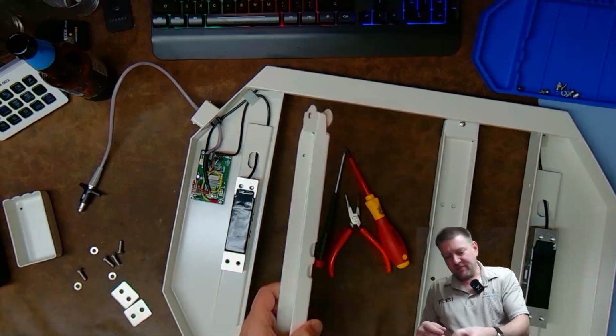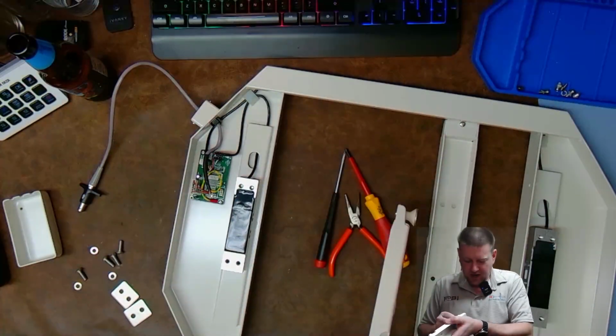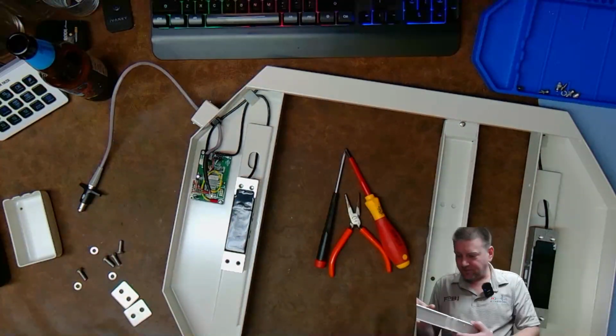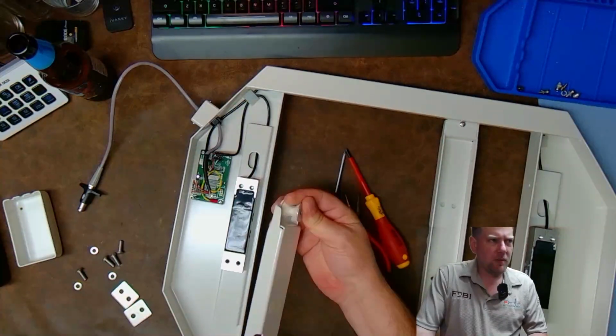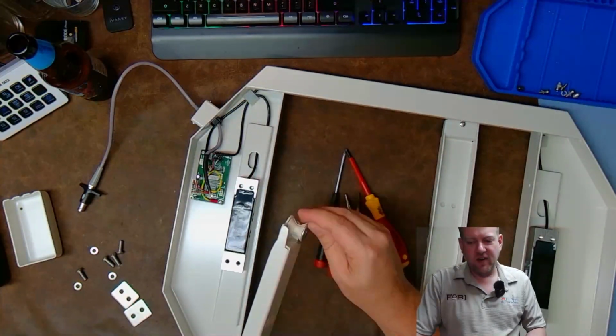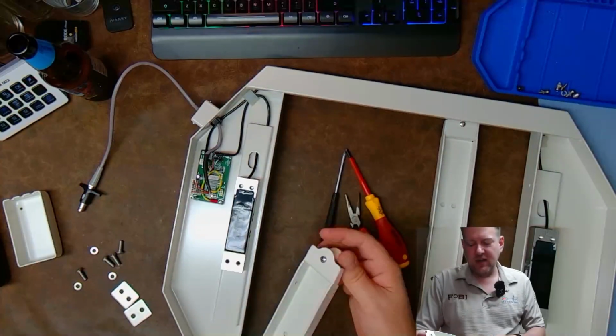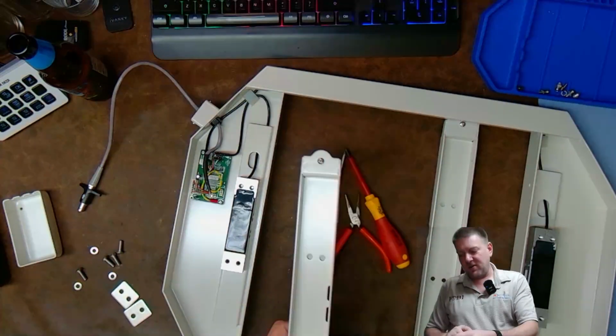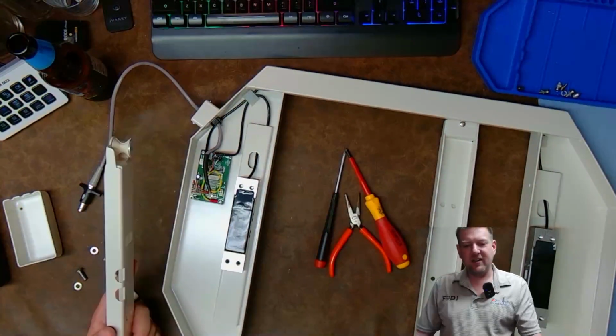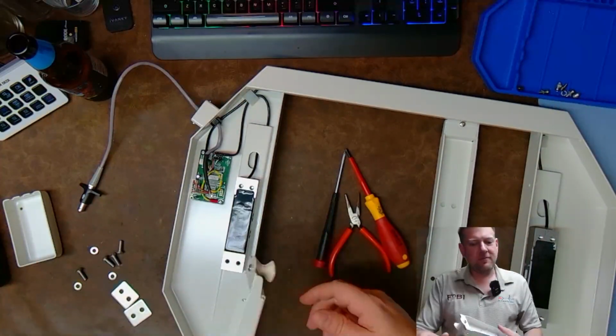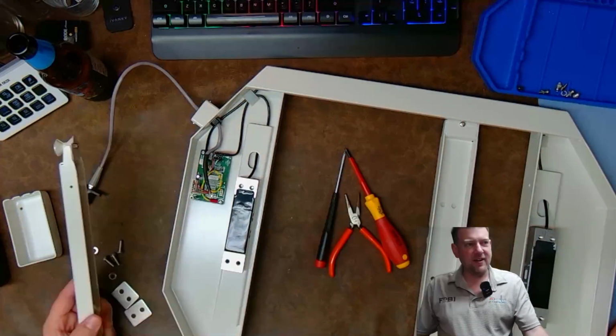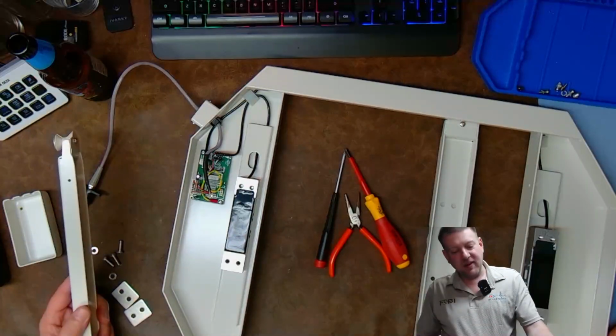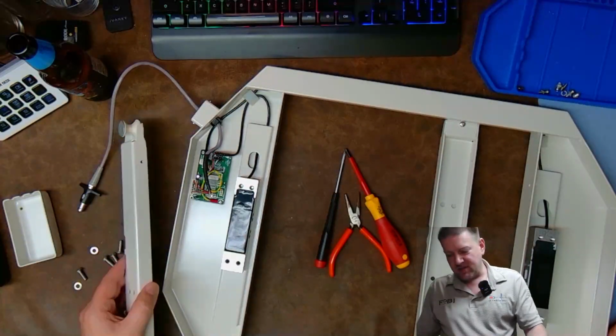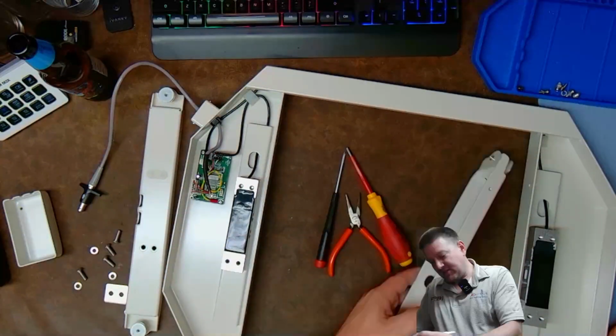You're good. Now, the other thing that you should always check on these scales is we've got rubber standoffs. You want to make sure that these here are not degrading. And you want to make sure that your fasteners are all tight. Because if your fasteners aren't tight or these rubbers are degrading, then your bed is not going to sit on there flat. And you're probably going to come up with some load errors. And that's it.